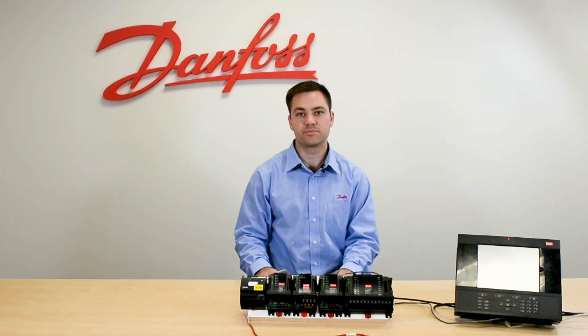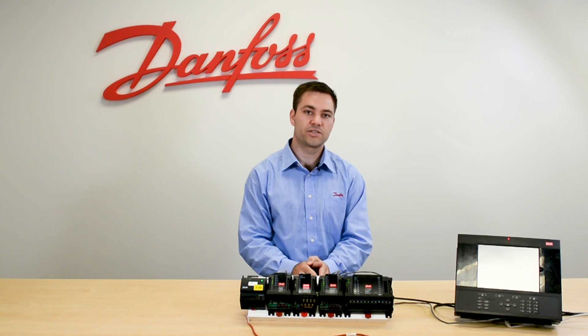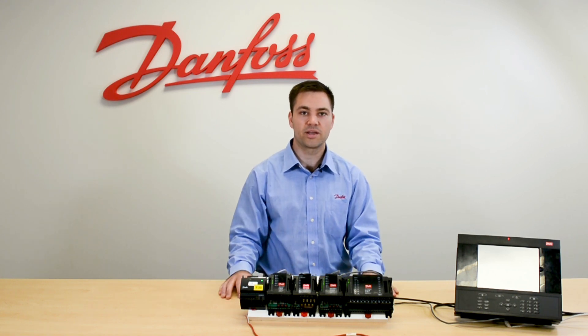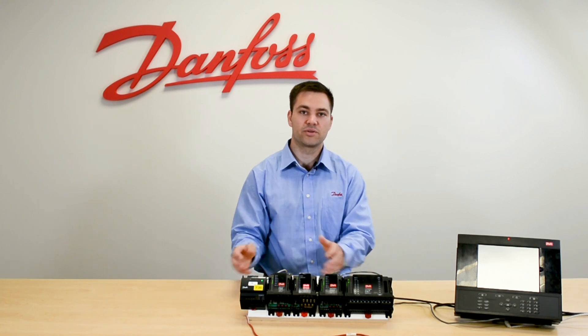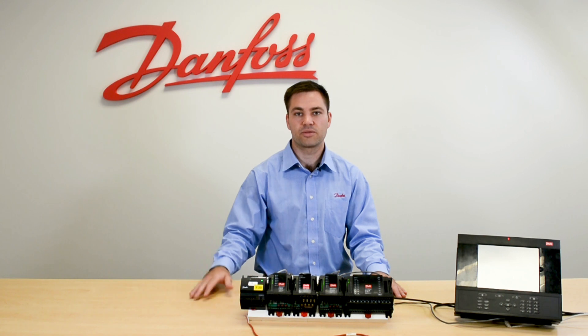Now both of these sensors are PT-1000, which means it's a positive temperature coefficient. So the baseline is at 32 degrees — you have 1000 ohms in your sensor — which is why we recommend calibrating in ice water at 32 degrees in an ice bath. Then you know you should have 1000 ohms and you should be at 32 degrees.